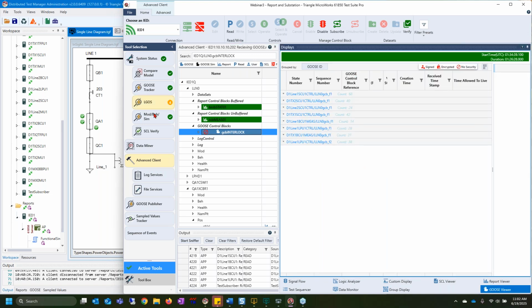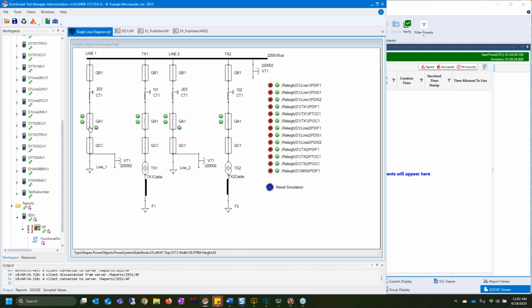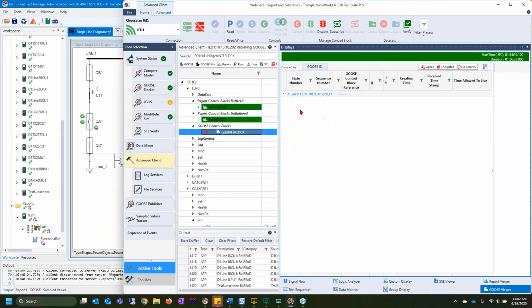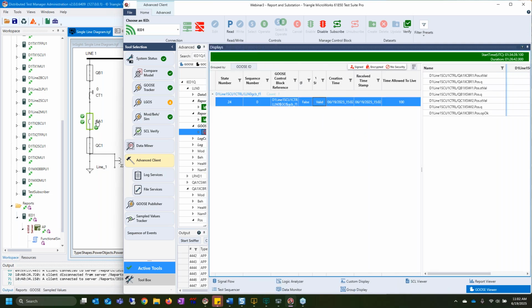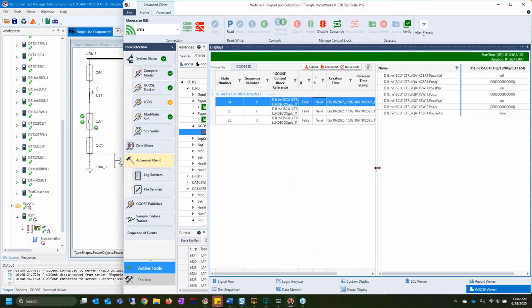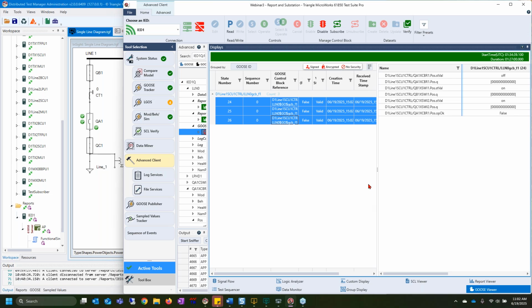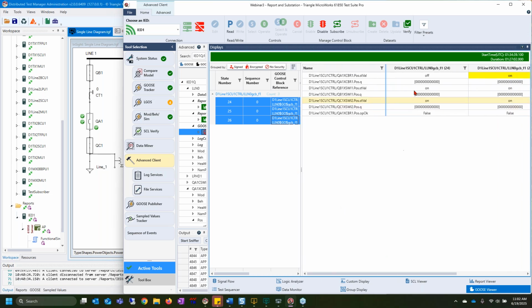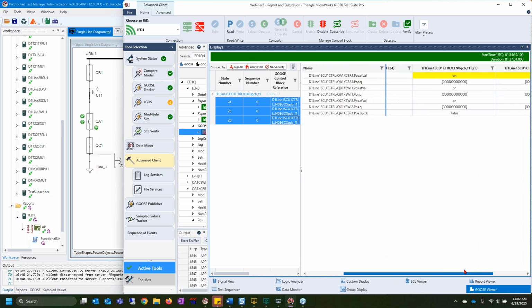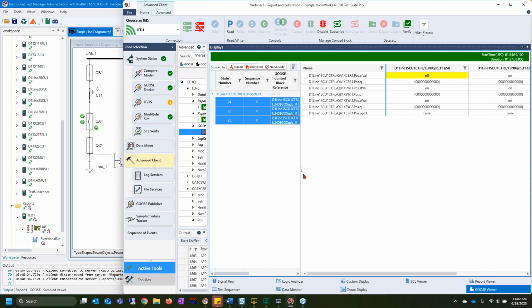And in here, you can see every time that I've changed this breaker, I've gotten a bunch of messages here. But if I go ahead and clear this out and toggle the breaker again, generate some events, sure enough, we'll see a GOOSE message come across in the GOOSE viewer. And just like before, maybe I changed this a few times, I wouldn't so much expect to see the measurement values, the amps on this, because typically you want the status values. It's something that other servers can quickly perform an action off of. And so sure enough, if I select all of these, you can see the full GOOSE stream here, and you'll be able to see as the value is changing, just like you would in the report viewer.